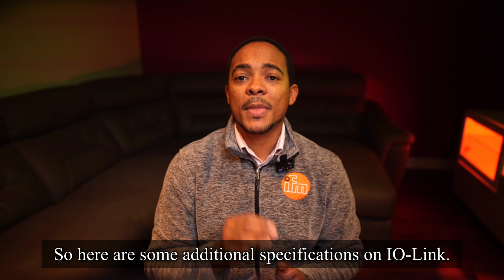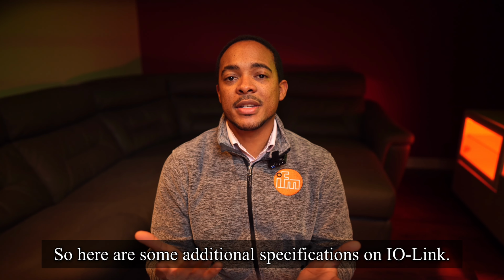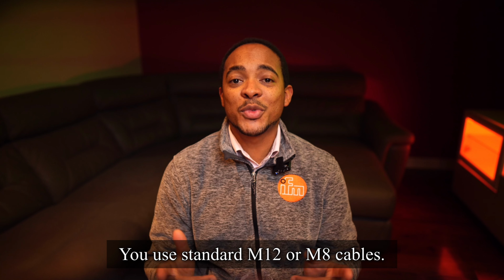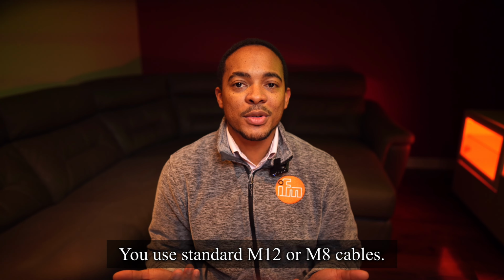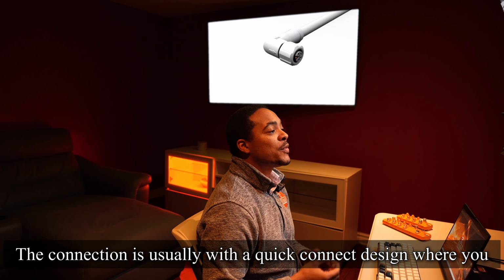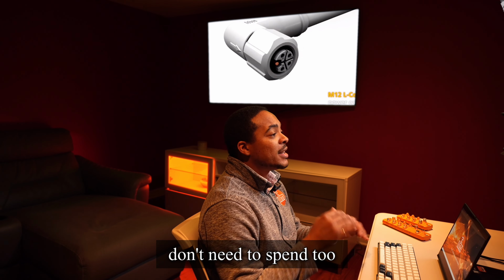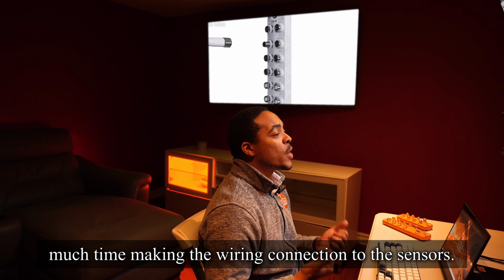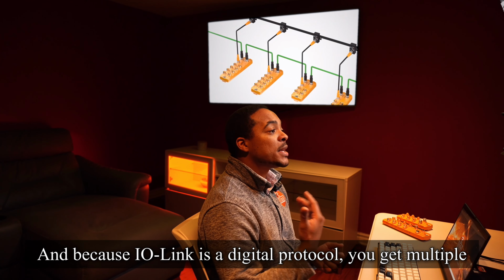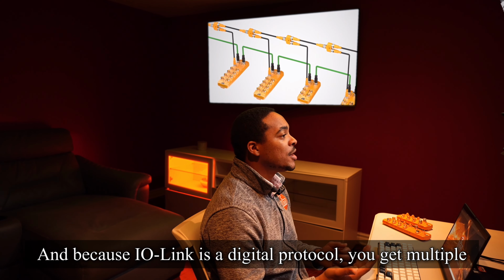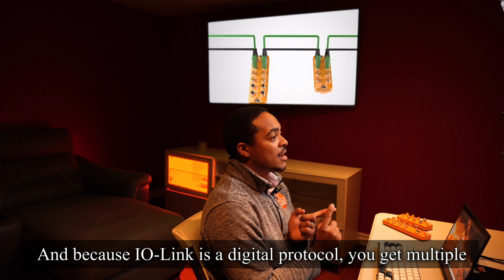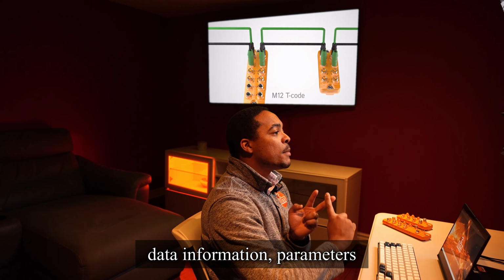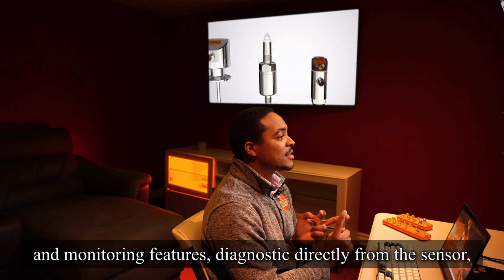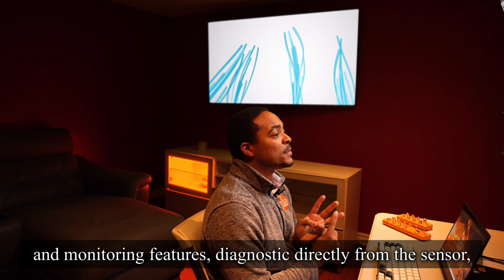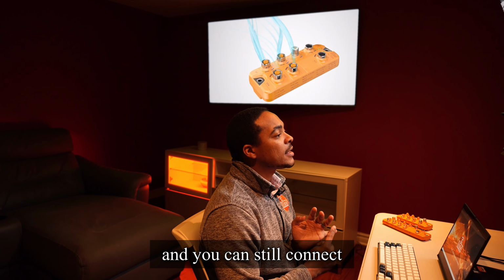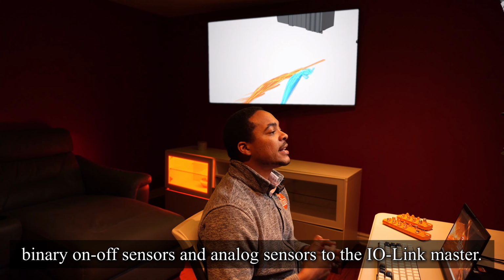So here are some additional specifications on IO-Link. You use standard M12 or M8 cables. The connection is usually with a quick connect design where you don't need to spend too much time making the wiring connection to the sensors. And because IO-Link is a digital protocol, you get multiple data information, parameters and monitoring features, diagnostic directly from the sensor, and you can still connect binary on-off sensors and analog sensors to the IO-Link master.